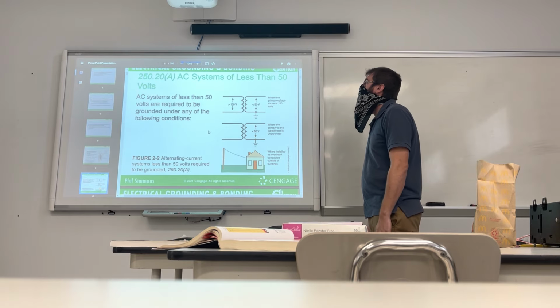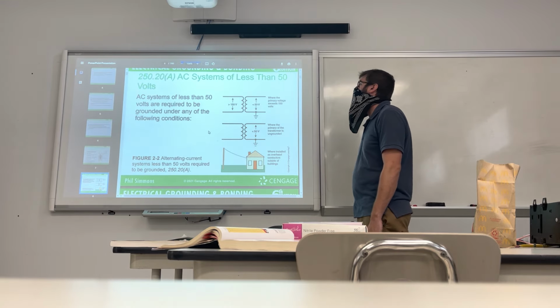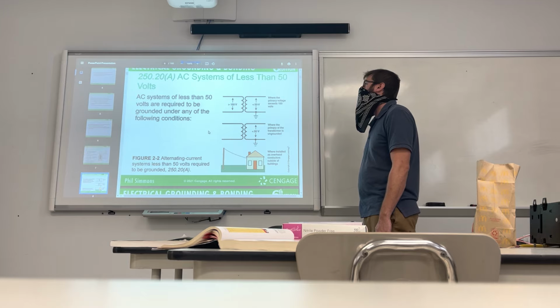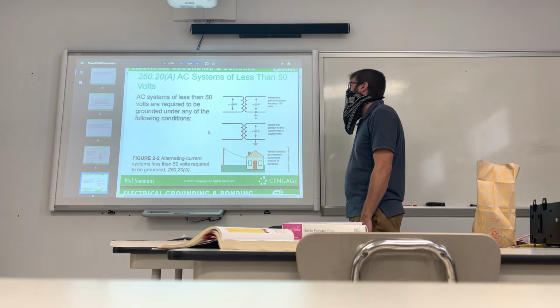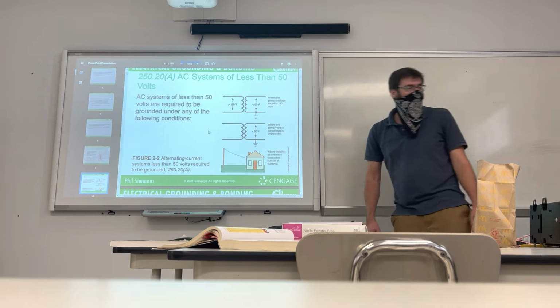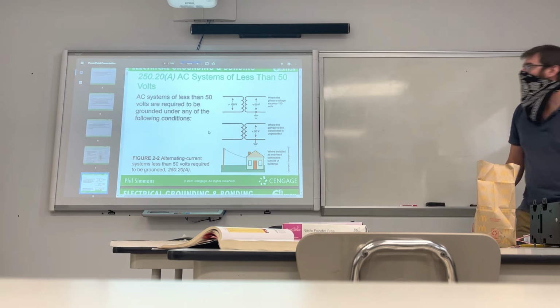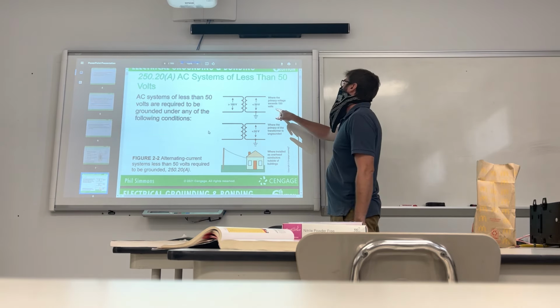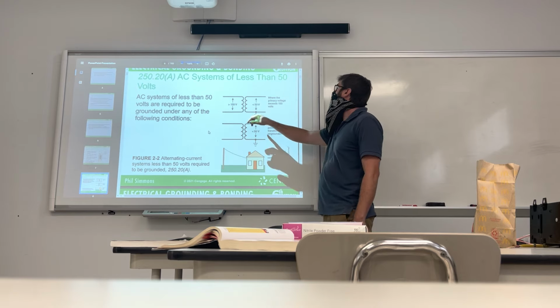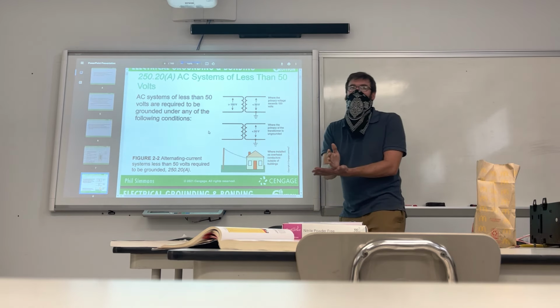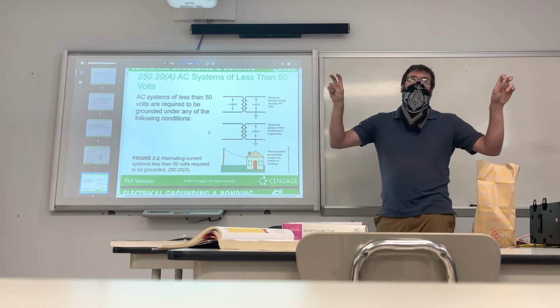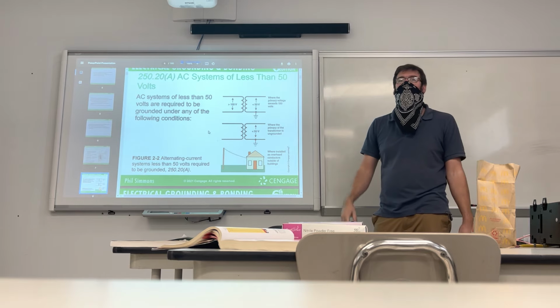250.20(A). AC systems of less than 50 volts. AC systems of less than 50 volts are required to be grounded under any of the following conditions. I wish they would give you that in the slide. Yeah, where the primary voltage exceeds 150 volts. Because 50 volts is like the threshold, right? That's what they consider electricity to be dangerous above 50 volts.